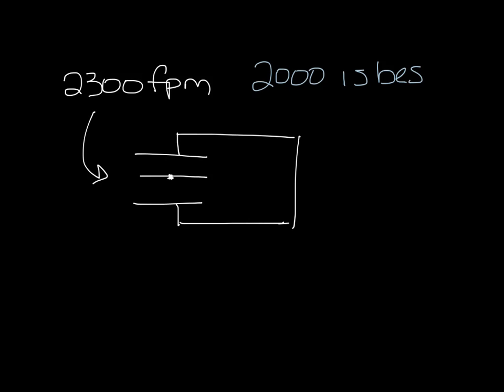So let's draw a single duct box. And this is the damper in the inlet. In the podcast on VAV box sizing, I said that you don't want to exceed 2,300 feet per minute in the inlet. Ideally, you'd be closer to 2,000 feet per minute.